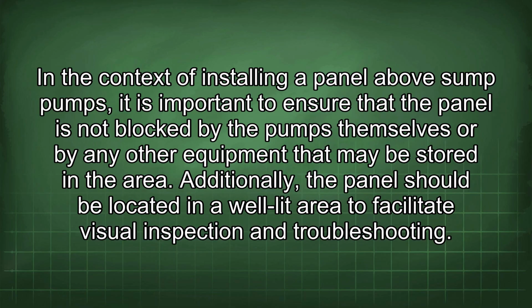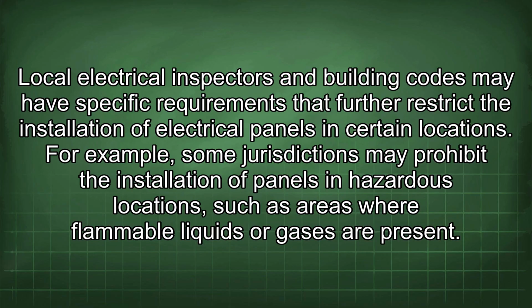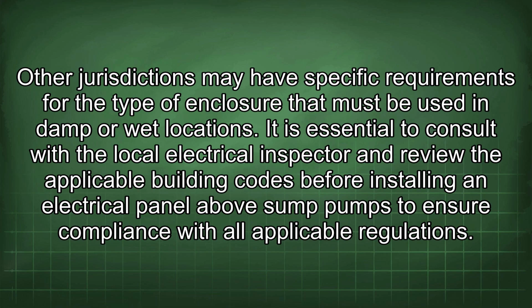In the context of installing a panel above sump pumps, it is important to ensure that the panel is not blocked by the pumps themselves or by any other equipment that may be stored in the area. Additionally, the panel should be located in a well-lit area to facilitate visual inspection and troubleshooting. Local electrical inspectors and building codes may have specific requirements that further restrict the installation of electrical panels in certain locations. For example, some jurisdictions may prohibit the installation of panels in hazardous locations, such as areas where flammable liquids or gases are present. Other jurisdictions may have specific requirements for the type of enclosure that must be used in damp or wet locations. It is essential to consult with the local electrical inspector and review the applicable building codes before installing an electrical panel above sump pumps to ensure compliance with all applicable regulations.